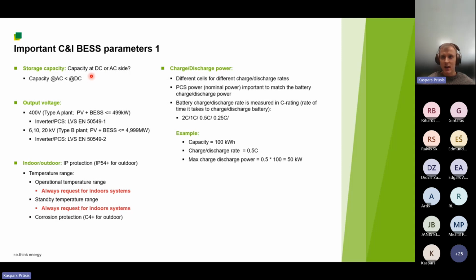want at the AC side, which means usable capacity, because the capacity of the battery will usually be higher than the one that you will be able to get on the system output due to efficiency of these battery management systems, battery management system modules, as well as inverters, etc. So on the AC side, you will always get less power. So these are things that you need to consider when talking about the capacity of the battery.